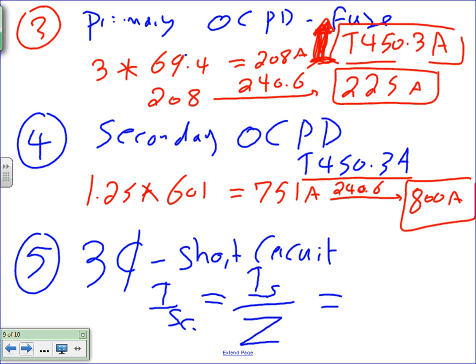For the short circuit, guys, this is a piece of cake. The short circuit is almost always on the secondary. So you take 601 divided by the impedance, which is 0.05, right? And that will get you a healthy 12,000 amps, give or take. 12,000 amps. If you want to write this Z, the impedance, the current is on the secondary, always the secondary. Any question, guys? Any question? It's okay. I'll finish this one in a second here. Okay, that's about it.